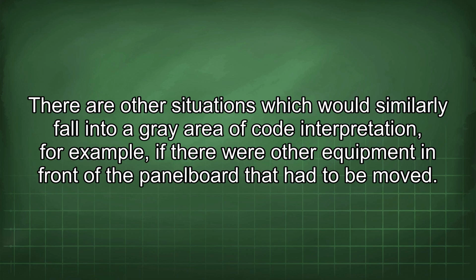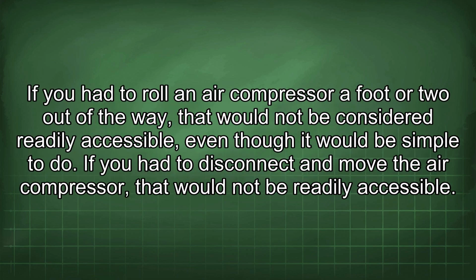For example, if there were other equipment in front of the panel board that had to be moved. If you had to roll an air compressor a foot or two out of the way, that would not be considered readily accessible, even though it would be simple to do. If you had to disconnect and move the air compressor, that would not be readily accessible.